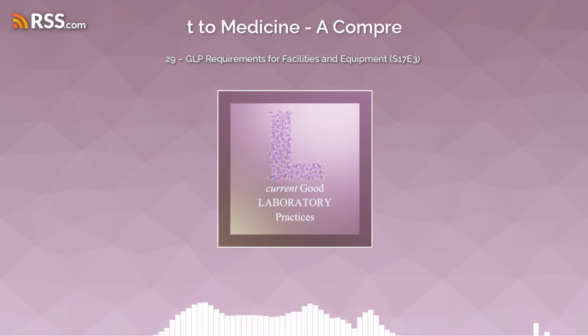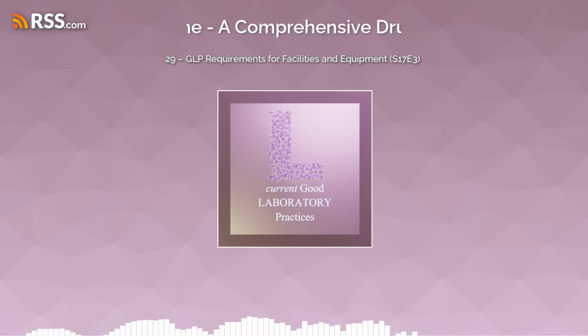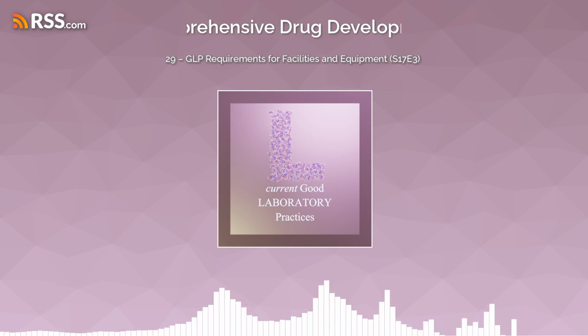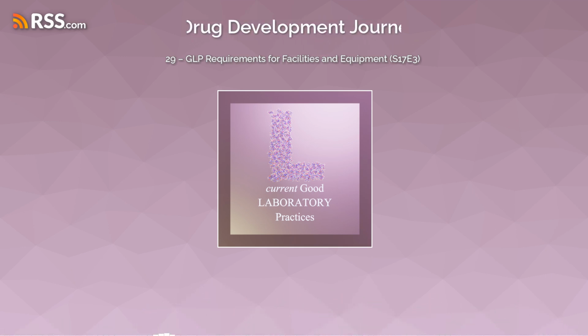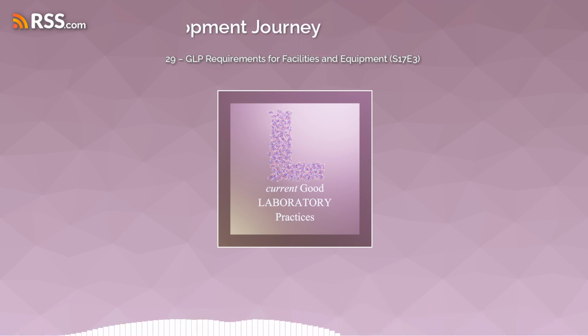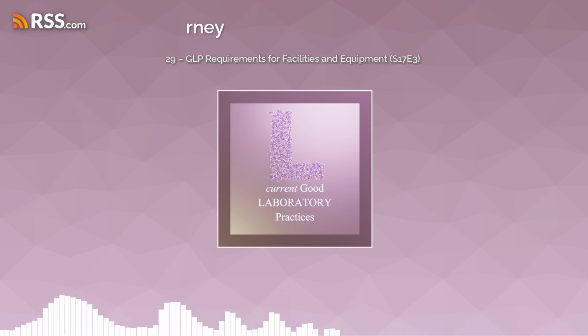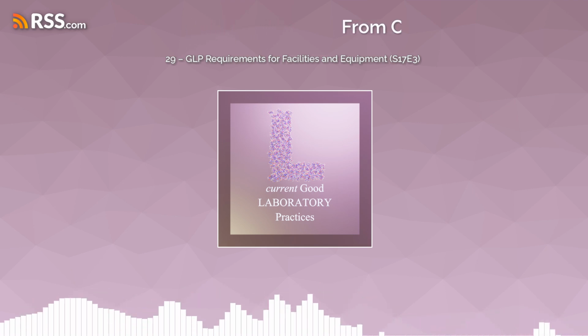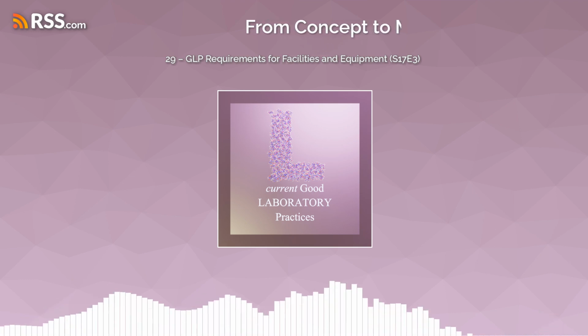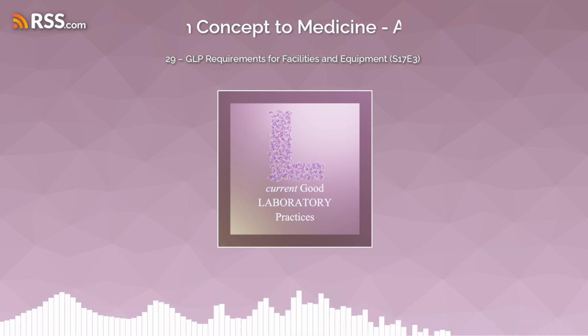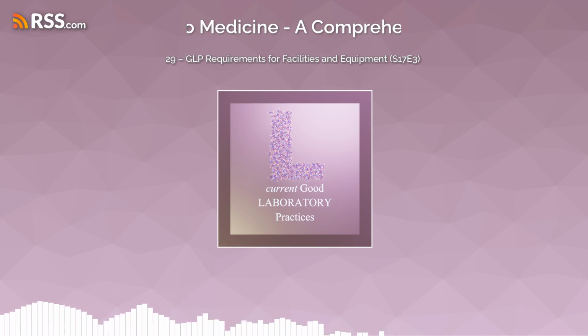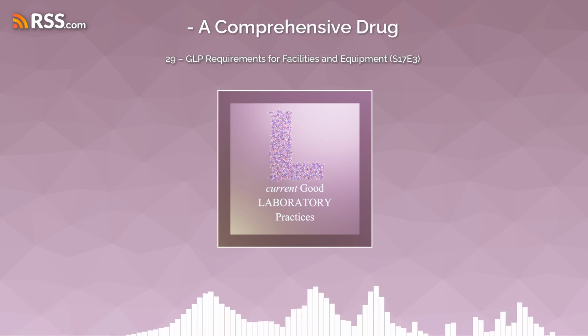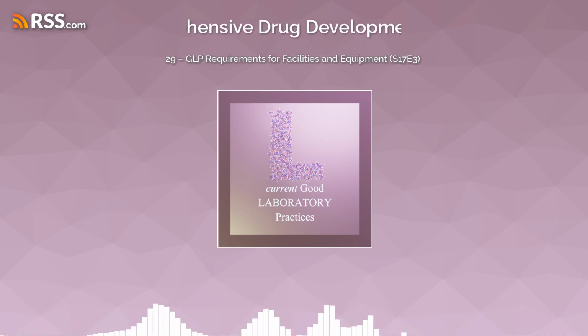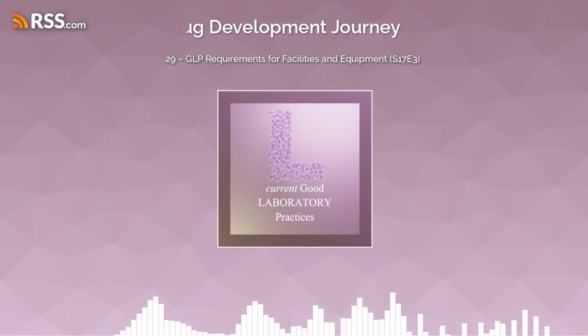The transcript specifically mentioned moving a big piece of equipment, like an HPLC system. Just relocating it within the lab could impact its performance, even if it seems like a small change. Yeah, even subtle things like slight variations in airflow or vibrations in a new location can throw things off. So requalification is key to make sure everything is still working as it should. And of course, it's all documented, every single step, every result. So there's a paper trail, or probably a digital trail these days, showing that everything was done by the book.